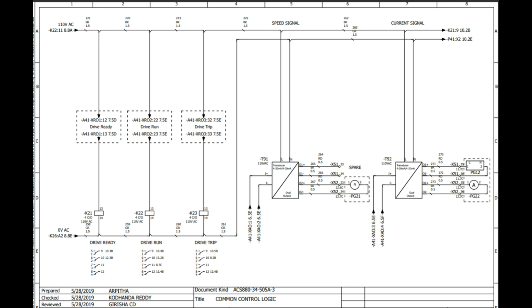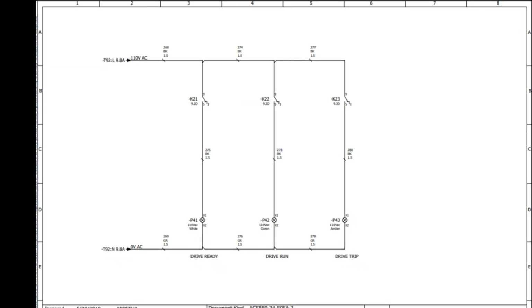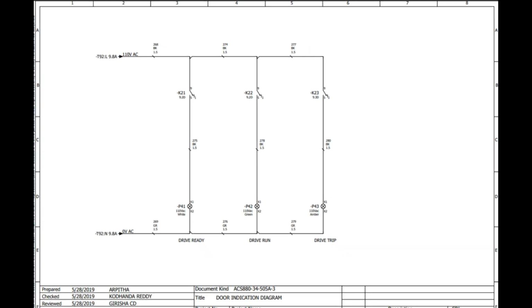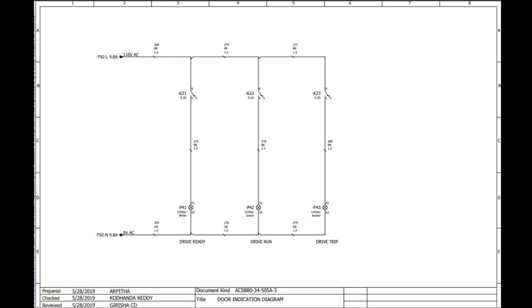Next we'll come to another page. The three relays we have seen give the drive ready, drive running or drive trip indication. How will the layman, how will the technician get to know whether the drive is running or it has tripped? For that, there are indicators: a white light, green light for running, and amber for trip. All three are provided with three different parts of the auxiliary contactor. So K21, if the drive is ready, it will get NC and this LED will glow, 110 volt again. Similarly K22 for the running indication, green, and K23, one part of the contactor, is used for drive trip. This is how the indication system works.